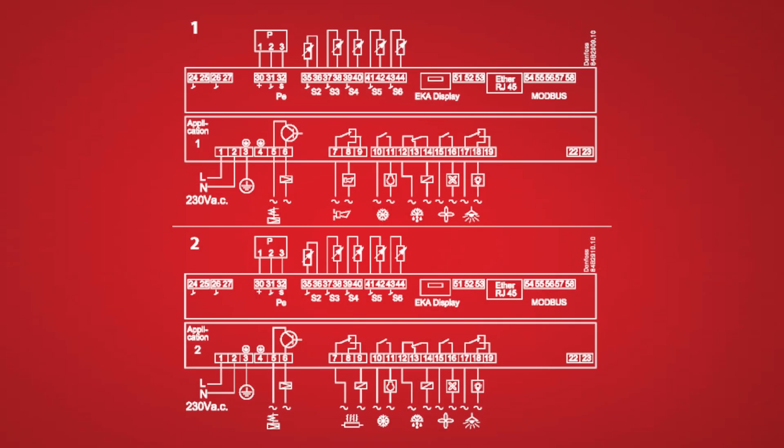Across the bottom of the controller we have the relay connections. First we have the AKV relay. This solid state relay is used to cycle the AKV valve for pulsing liquid into the coil. Then we have the evaporator fans, defrost, lights, and anti-sweats.